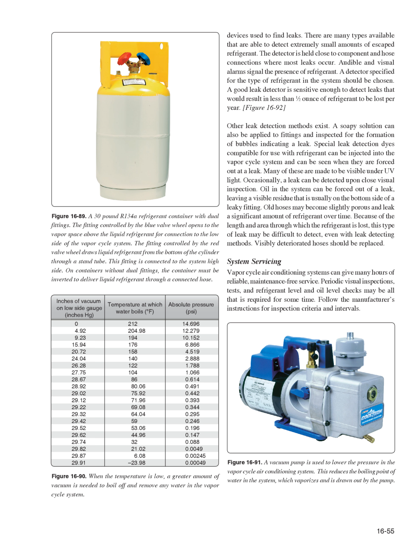Occasionally, a leak can be detected upon close visual inspection. Oil in the system can be forced out of a leak, leaving a visible residue that is usually on the bottom side of a leaky fitting. Old hoses may become slightly porous and leak a significant amount of refrigerant over time. Because of the length and area through which the refrigerant is lost, this type of leak may be difficult to detect, even with leak detecting methods. Visibly deteriorated hoses should be replaced.